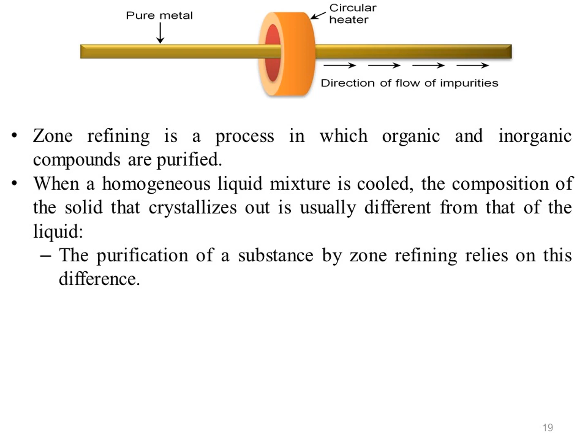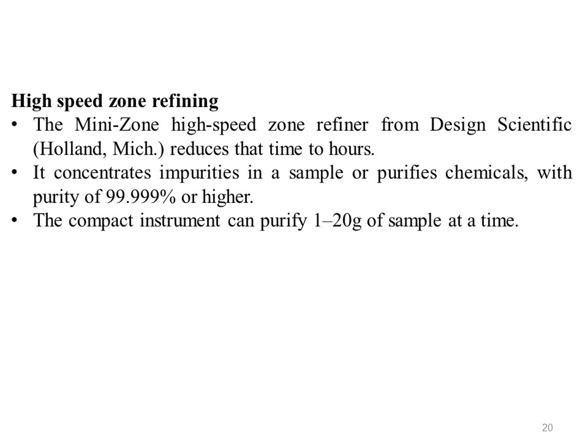High-speed zone refining. While used successfully to purify organic chemicals, zone refining is time-consuming. Purification takes days. The mini-zone high-speed zone refiner from Design Scientific reduces that time to hours. It concentrates the impurities in a sample or purifies chemicals with purity of 99.999% or higher. The compact instrument can purify 1 to 20 grams of sample at a time. Controls include melt temperature, freeze temperature and zone migration rate. Any thermally stable sample that is solid between -10 degrees and +300 degrees can be purified by this method.